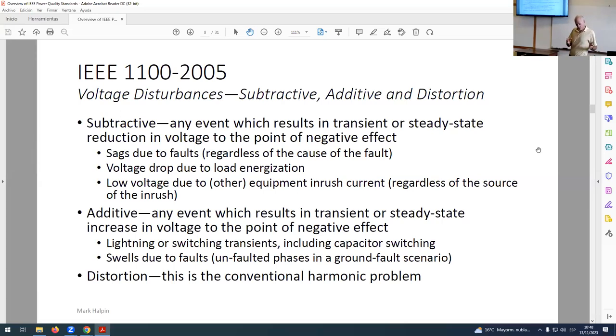And there are disturbances associated with distortion. They don't really change the RMS value much, but they corrupt the voltage. So the subtractive and additive disturbances tend to increase or decrease the RMS voltage, while the distortion category doesn't change the RMS value much but disrupts the quality. These were the three kinds of voltage disturbances the Emerald Book considered. In 1980, this was not really a big problem in general. Lightning's been there forever. As long as we've had power systems, they're subject to short circuit faults and therefore sags. So most of the attention in the Emerald Book is on those two categories, with just a little bit on harmonics.